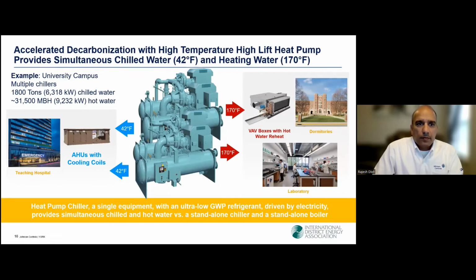So this is a good representation of simultaneous cooling and heating mode. In this particular example, we have a cooling load of 1,800 tons, and we have done our best to include the metric units as well. 1,800 tons or 6 megawatt of cooling load from a hospital. So this is our evaporator source. We also have a coincidental heating load of 31,500 MBH or 31 million BTUs, approximately 9 megawatts of heating capacity that exists from academic buildings, labs, dorms, college campus. So this is our sink.